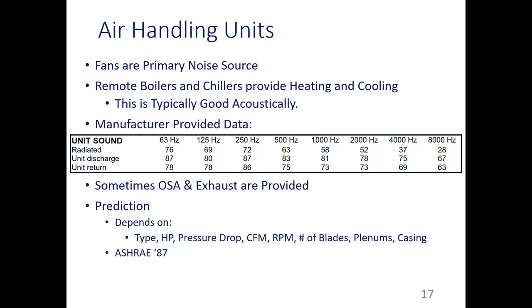If you have a pretty critical application, then you want to have your air handling units, and then you want to remote the chillers and the boilers and all that. It's more expensive to remote the chiller, but something that often is not considered in the less expensive, or what appears to be less expensive, option of just having a packaged unit is that once you have a packaged unit, you need to put in a concrete pad, and there's a lot more money in noise mitigation. If that was factored in, the remote chiller option would not look nearly as expensive by comparison.